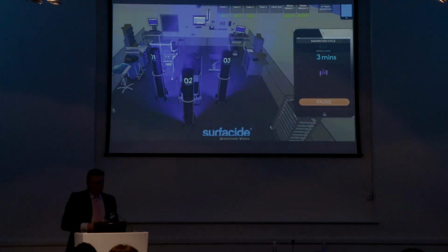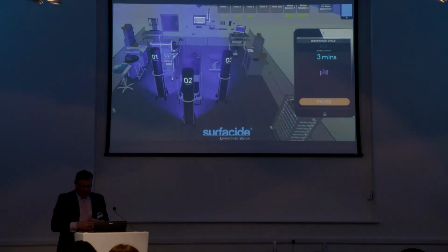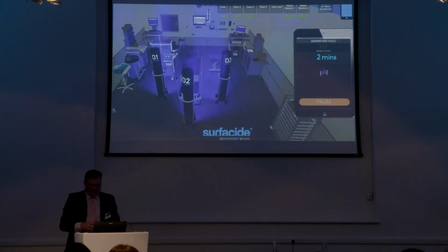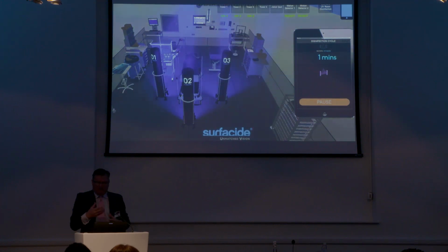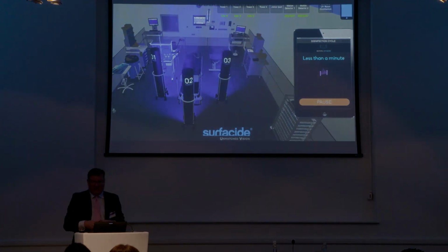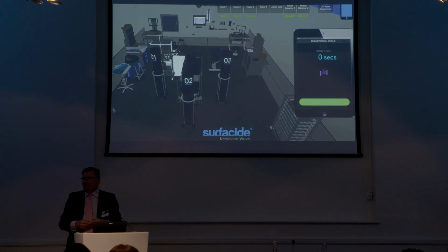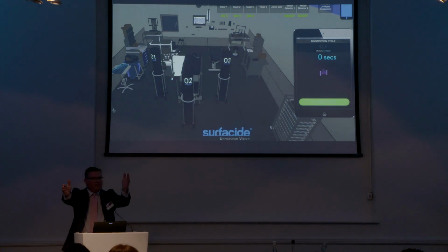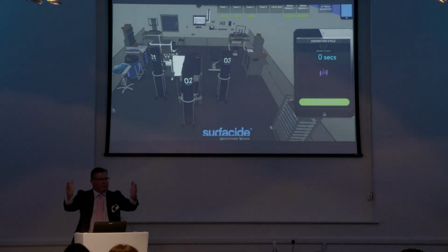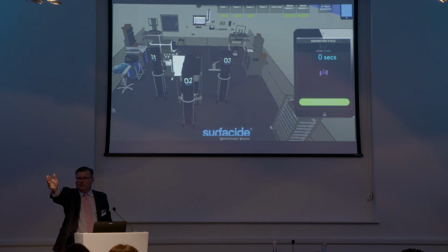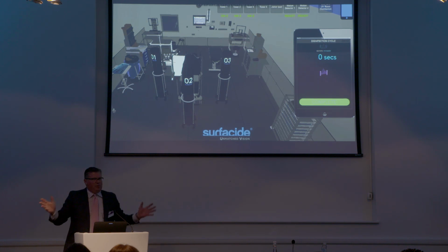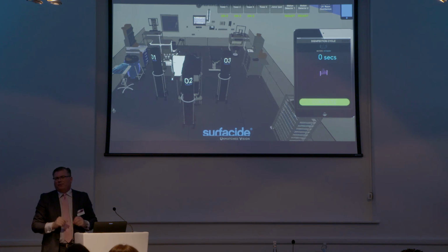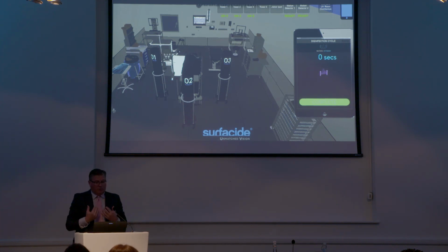Royal Manchester Children's Hospital has been using Surfacide here in the UK for just about 2.5 to 3 years. And they're doing literally dozens of cycles each day in exactly this mode. In the multi-bedded bays and wards, they start and stop where the patient screen or the curtain ends, and the energy is only going from one corner of the screen to the wall to the other corner of the screen to the wall, and we're disinfecting the entire bed and all of the equipment in the forward portion. No energy is going rearward.